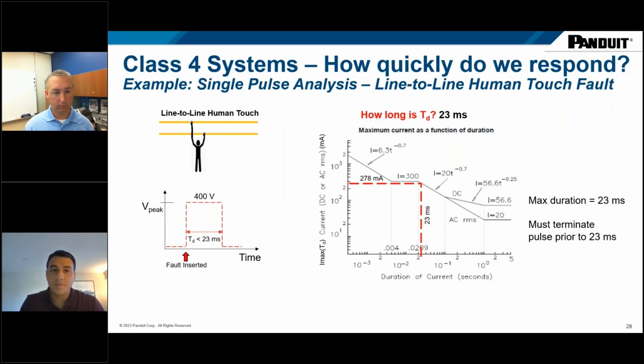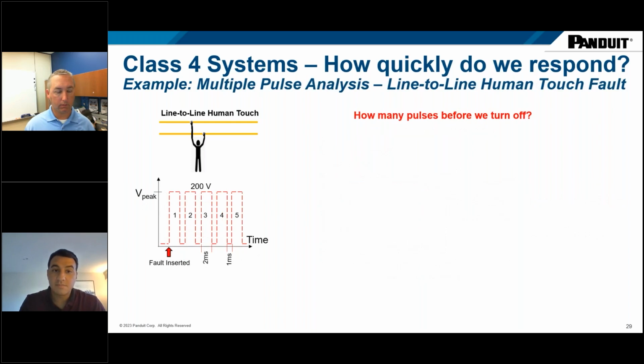It gets a little bit more complicated if you have a system that maybe has multiple pulses, because there's something here that's called the accumulation effect. So if someone touches the copper conductors, they could be exposed to multiple pulses, and every time they're exposed to a pulse, the limit of that energy that they can be exposed to drops significantly. And so after a certain number of pulses, the standard would require you to again turn power off so that there's no harm to that person.